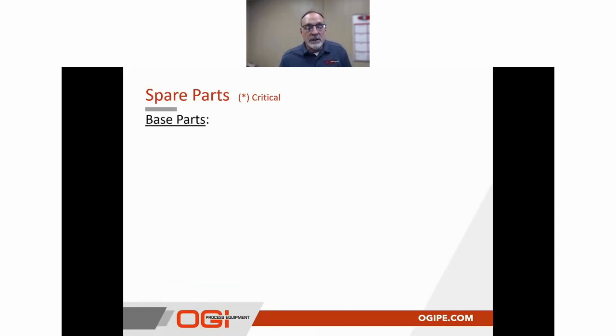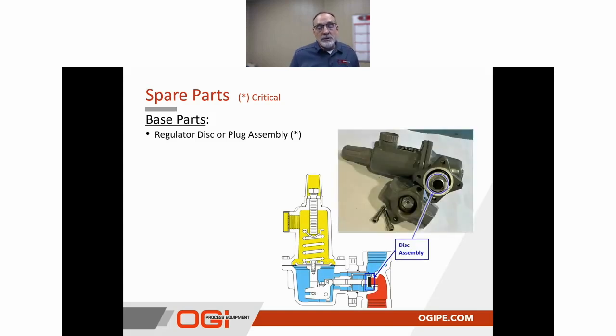In this case, we're going to take the next few minutes and talk about different spare parts at different levels, from the base parts levels that are most common to the heaters to those that are more specific to unique burner or heater applications. So we're going to start with the base parts. The most common part that you're going to find on any heater is going to be the regulator. One of the easiest things to maintain as a spare part is the disc, and one of the more used or potential fail points of a regulator is the plug assembly on that regulator.